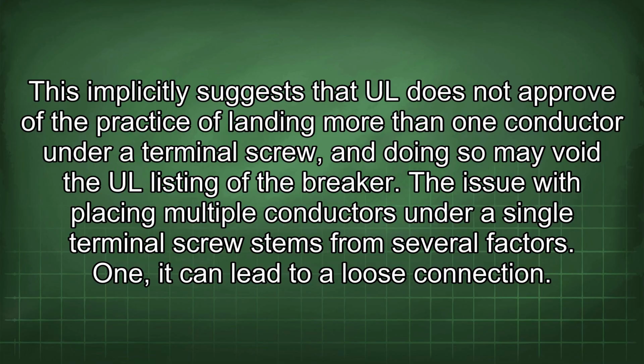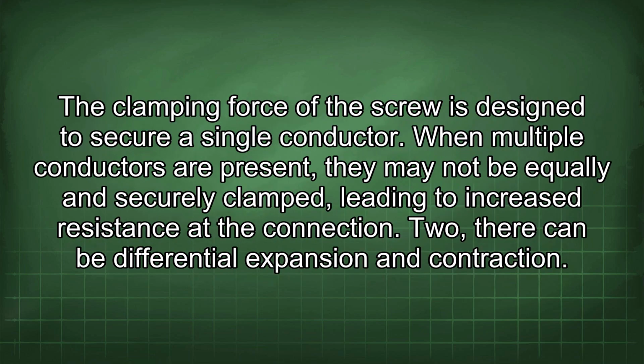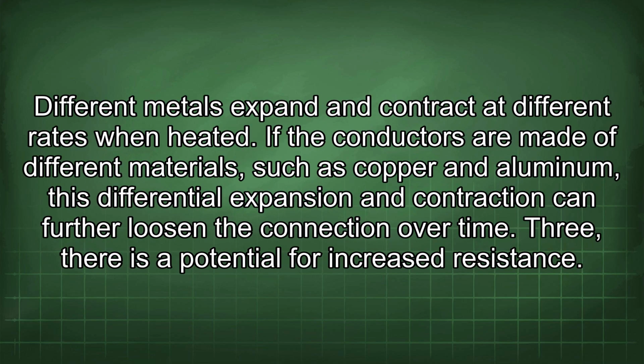The issue with placing multiple conductors under a single terminal screw stems from several factors. 1. It can lead to a loose connection. The clamping force of the screw is designed to secure a single conductor. When multiple conductors are present, they may not be equally and securely clamped, leading to increased resistance at the connection. 2. There can be differential expansion and contraction. Different metals expand and contract at different rates when heated. If the conductors are made of different materials, such as copper and aluminum, this differential expansion and contraction can further loosen the connection over time.